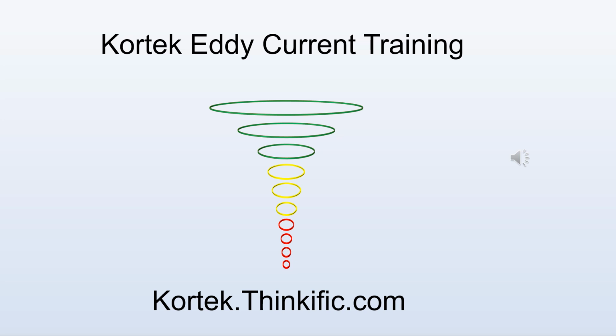However, if direct current is flowing through a primary conductor and a secondary conductor is constantly moving relative to the primary conductor, eddy currents will be produced in the secondary conductor, which will produce an opposing secondary magnetic field. If an oscillator is used to energize the primary conductor with alternating current, the primary magnetic field will be an alternating magnetic field, which will induce alternating currents, called eddy currents, in the secondary circuit.